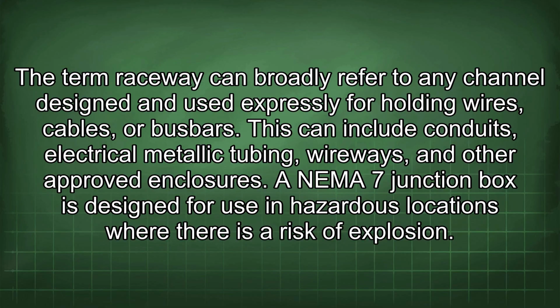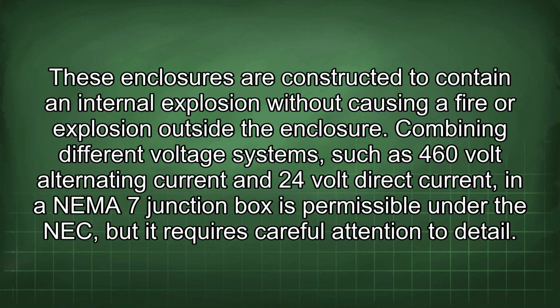A NEMA 7 junction box is designed for use in hazardous locations where there is a risk of explosion. These enclosures are constructed to contain an internal explosion without causing a fire or explosion outside the enclosure. Combining different voltage systems, such as 460-volt alternating current and 24-volt direct current, in a NEMA 7 junction box is permissible under the NEC, but it requires careful attention to detail.